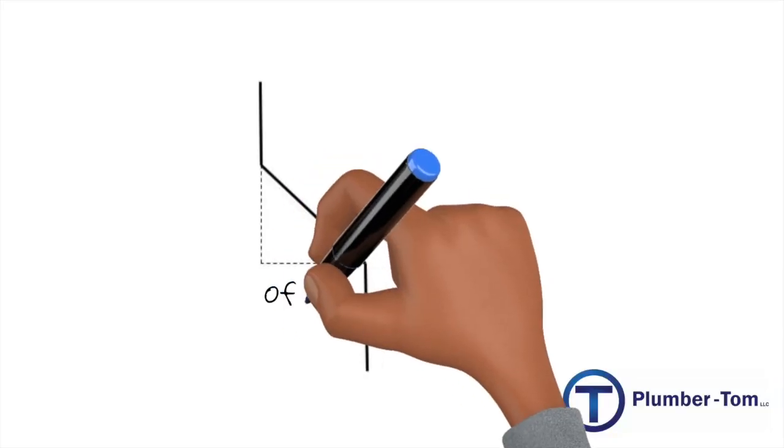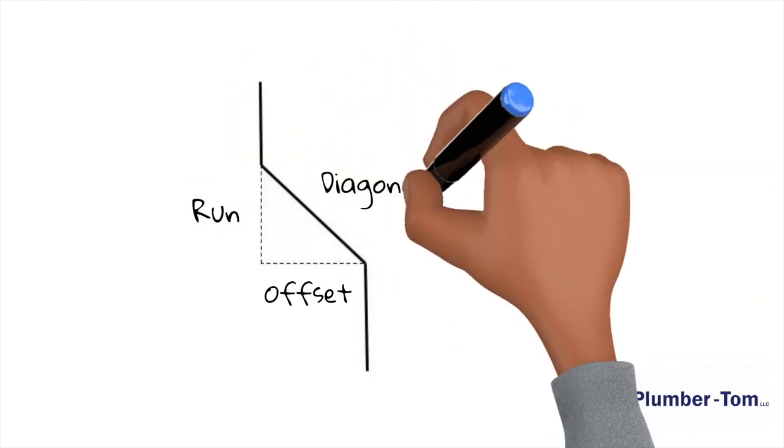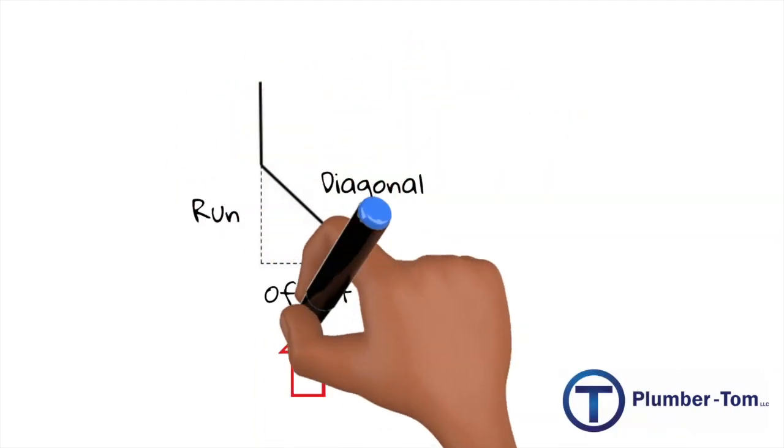In order to do the calculations relating to a 45 degree offset, we need to be able to visualize the triangle created by the offset. The angle pipe is the diagonal of the triangle. The offset is the distance the center of the pipe has moved over from its original location. The run is how far the pipe travels as it is angling over to a new center location.